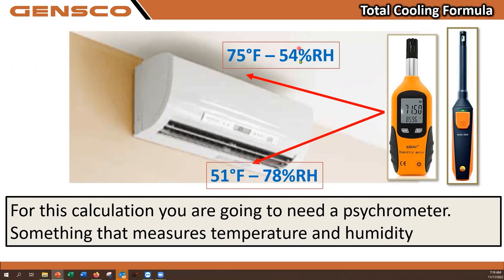Now, if this return air temperature or humidity itself was much higher than this, the higher that return air humidity is, the higher the humidity is going to be on your exit side. And this could be a clue when you're dealing with a unit that maybe has a mold issue. And everybody has, or at some point may have run into this, where you've got mold growing on the blower wheel inside a wall-mounted unit. It's probably due to very high humidity conditions within the space. I've seen the supply air humidity as high as 95, 98%, because the humidity in the room was high. And incidentally, the goal for our humidity for someone's comfort level within a space is about 50%. 45 to 50% is the ideal range for that to be at.